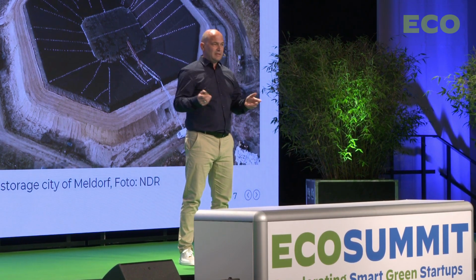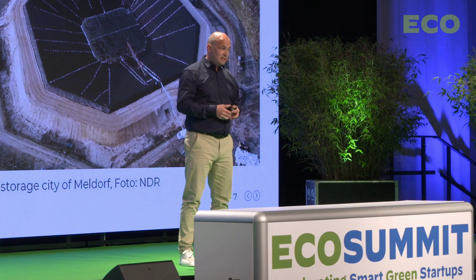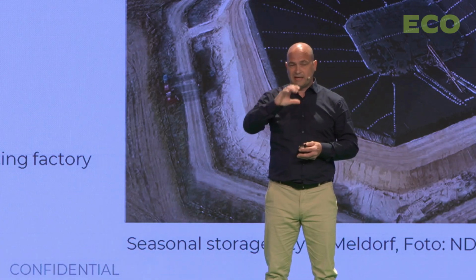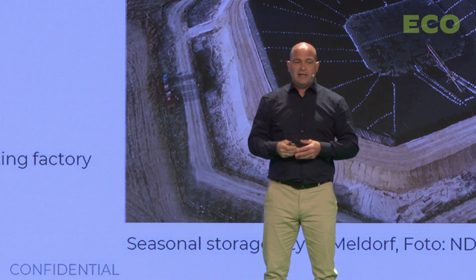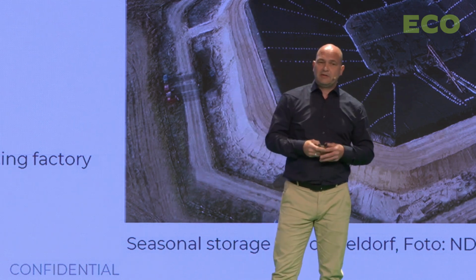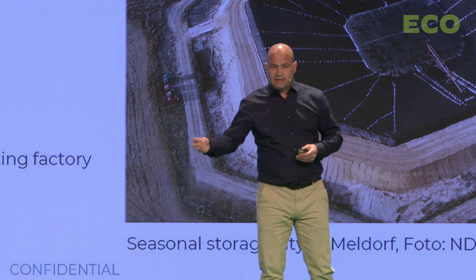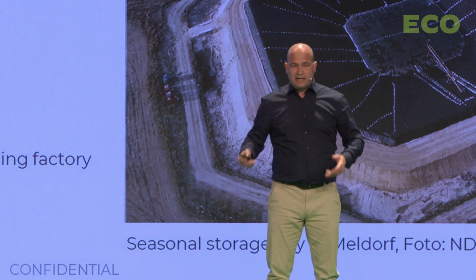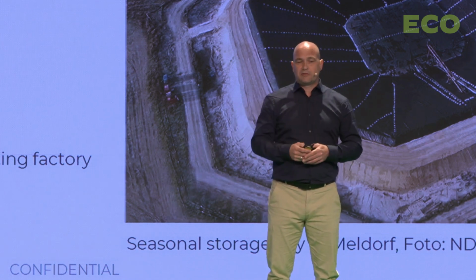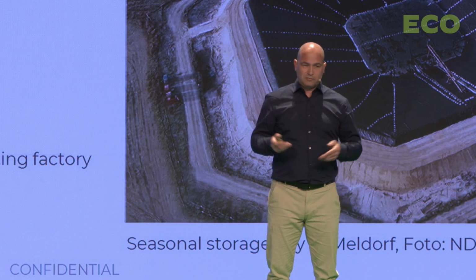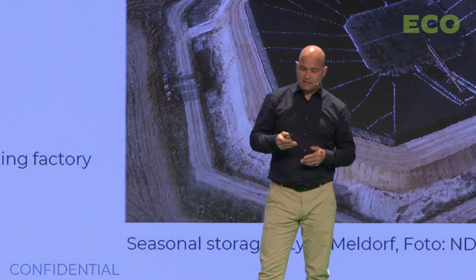This demonstrates the flexibility of the heat pump, because we don't need a cascade to cope with 90 degrees at the end of summer and 30 degrees at the end of winter. Also, in summer, if electricity is cheap, we use air as the heat source and lift 100K into the storage, thanks to the heat pump's high lift capability.